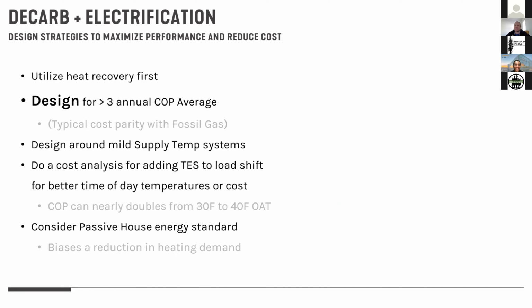You have to actually design your system. You cannot throw a heat pump in and read the label that is at the AHRI test standards at 40 degrees, 42 degrees. That test is useless in cold climates. Get the actual curve from the manufacturer. They're not going to want to share it with you. They're going to give you a bunch of pushback. Give them 5 temperature points, ask them what their capacity and COP are at those 5 points, and build your own curve. You have to design around the equipment.